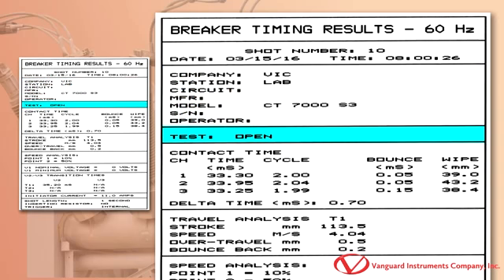The test type is shown in this section. In this case, we can see that the results are from an open test. The contact times are shown here in milliseconds. The equivalent times in cycles are shown in the cycle column. The measured contact bounce duration is listed here in milliseconds. The contact wipe distance is measured and printed under the wipe column. The wipe measurement is shown in millimeters or inches depending on the user's preference. The delta time is shown here. This is the difference between the fastest and slowest contact time.